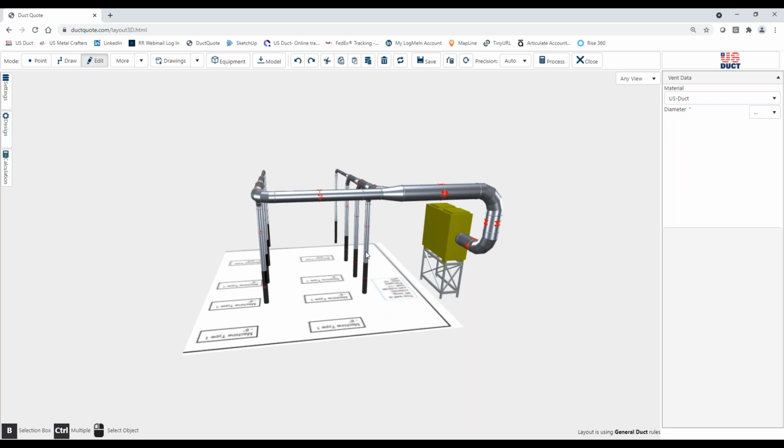We now verify the fan flow is within the range that we want, adjusting that damper if we need. And then we repeat steps 3 and 4 as we move out in the system further and further from the fan.